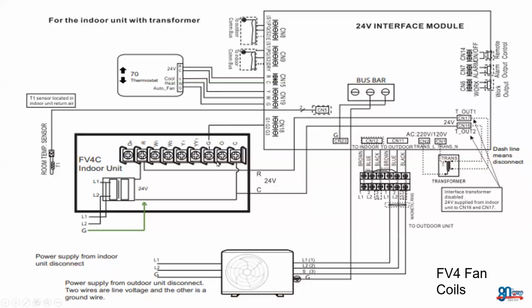We then take those same R and C, or hot and common terminals, and feed them over to the 24-volt interface on the T-OUT1 and T-OUT2 terminals, which essentially is going to be the input for 24 volts for our 24-volt interface module to power our thermostat. So instead of using the interface to step down to 24 volts, we're taking 24 volts from our FV4 indoor unit. Okay, so we have power coming in and signal provided from the ductless outdoor to the interface. And then from our FV4 indoor unit, we're going to supply 24 volts AC from the FV4 to the 24-volt interface to supply 24-volt power for our thermostat.